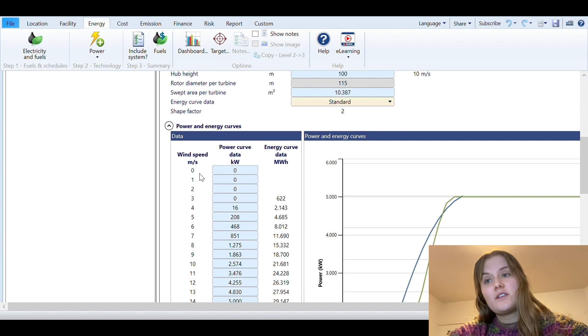It's shown in this table and in this graphic, this green line more specifically, which, as we can see, shows there's no power generated when the wind speed is lower than 4 meters per second, and it also maintains a rated power of 5 megawatts once we arrive at approximately 14 meters per second.